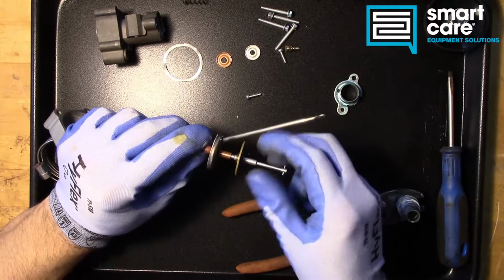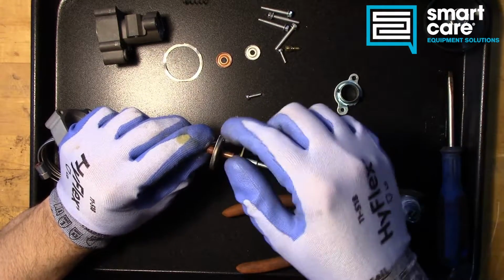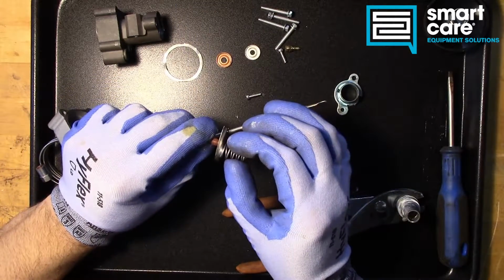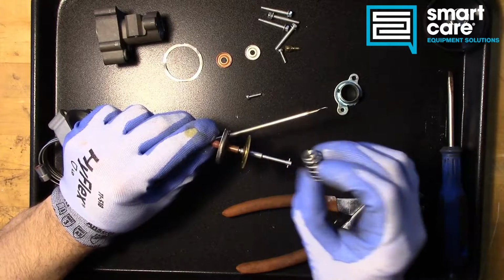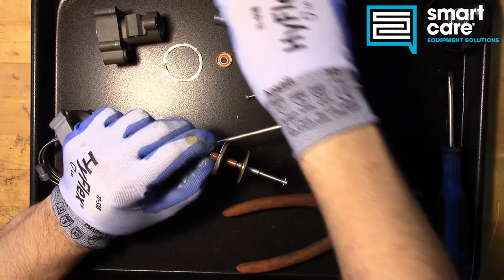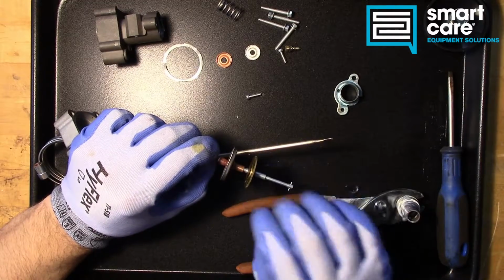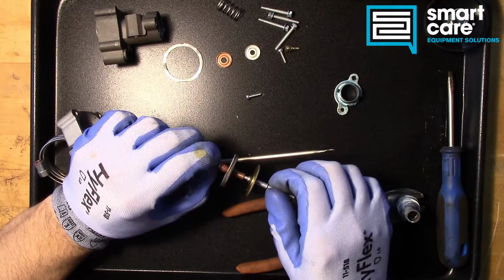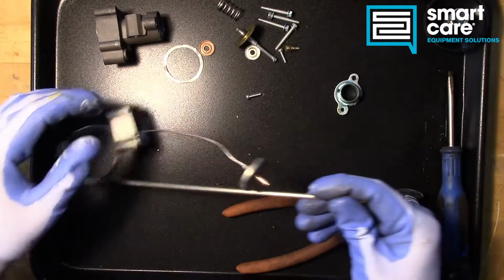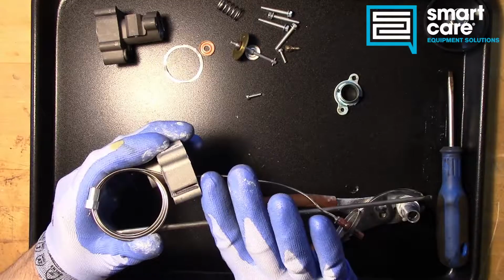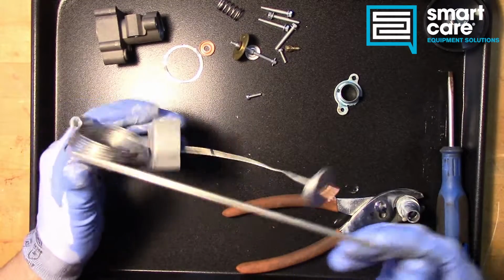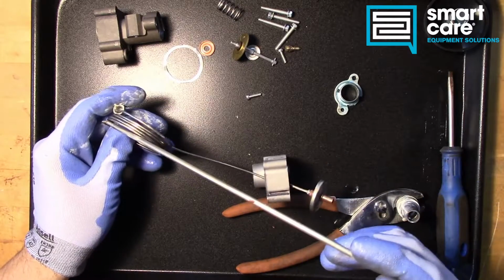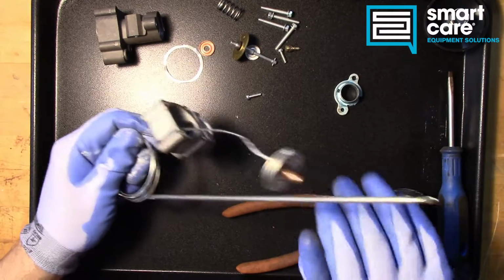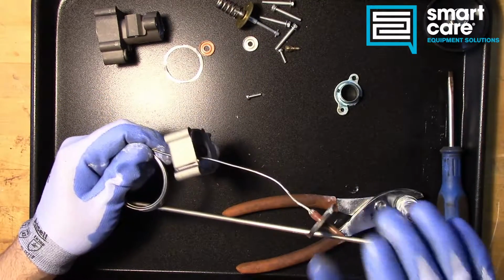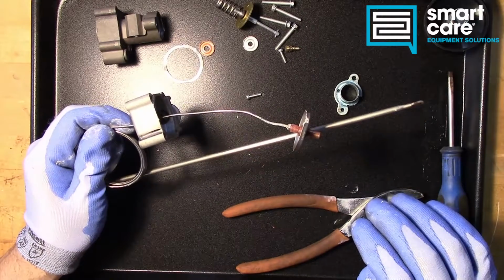What that means is you're changing this offset distance, but also changing the amount of spring pressure in here, because this spring is compressed by that threaded fitting. So it's going to have to fight that spring pressure even more with the bellows to close and shut off that gas flow. If this system fails, if this bellows fails, or this cap tube is kinked or compromised, or this bulb breaks off, because sometimes they'll break off back here, the thermostat's going to go into runaway. It's going to overheat because now there's no way to compensate against opening that valve. The bellows can't expand anymore. They've lost that fluid, that ability to open.